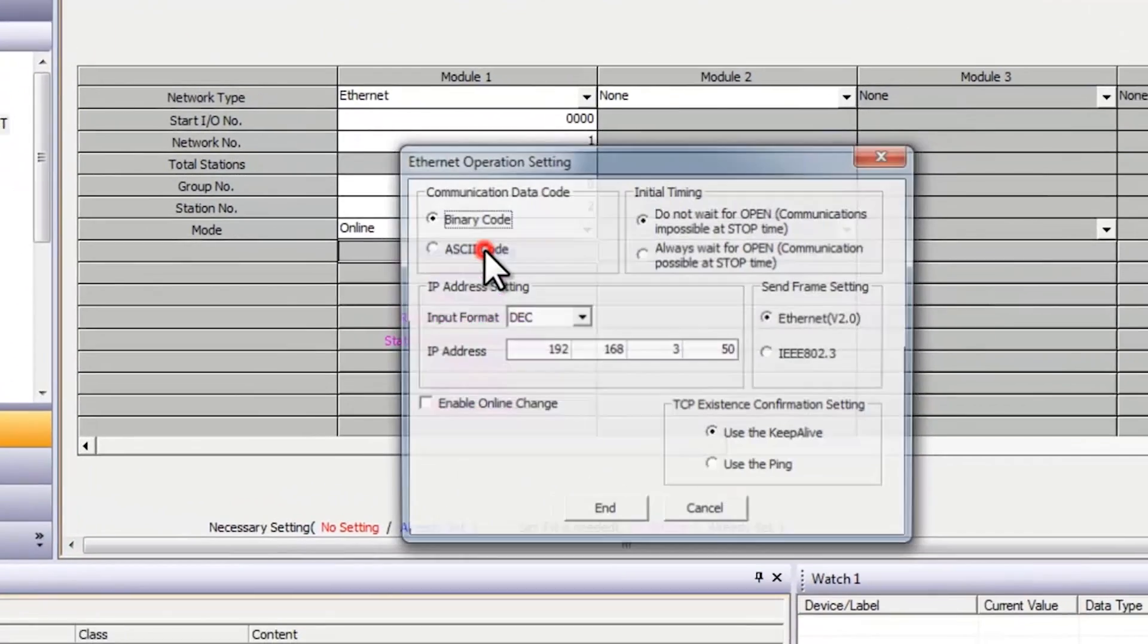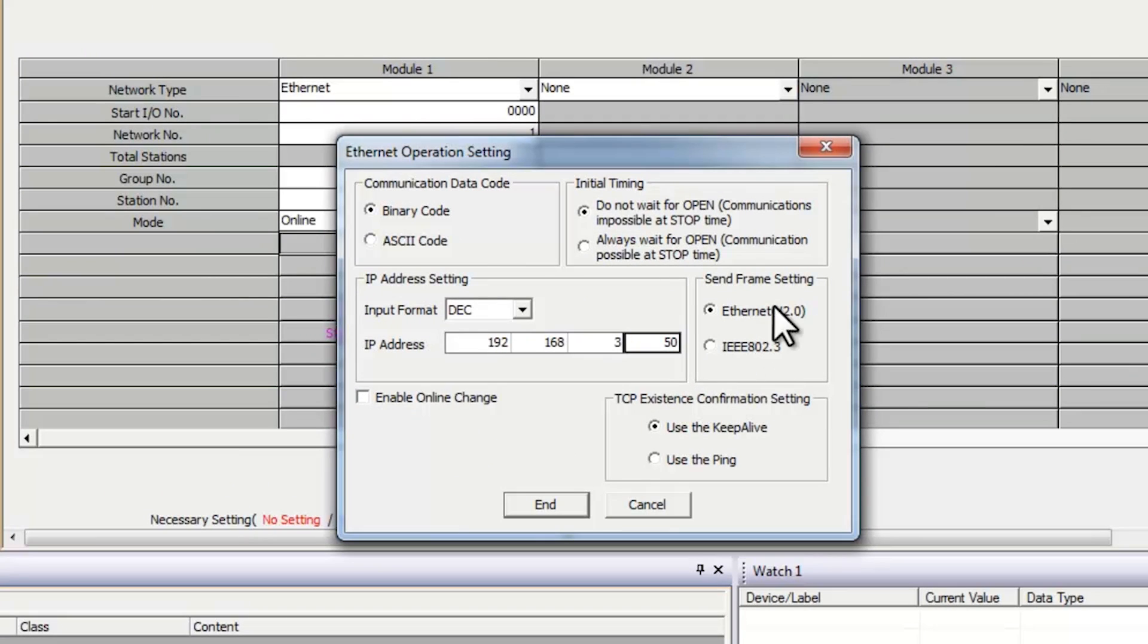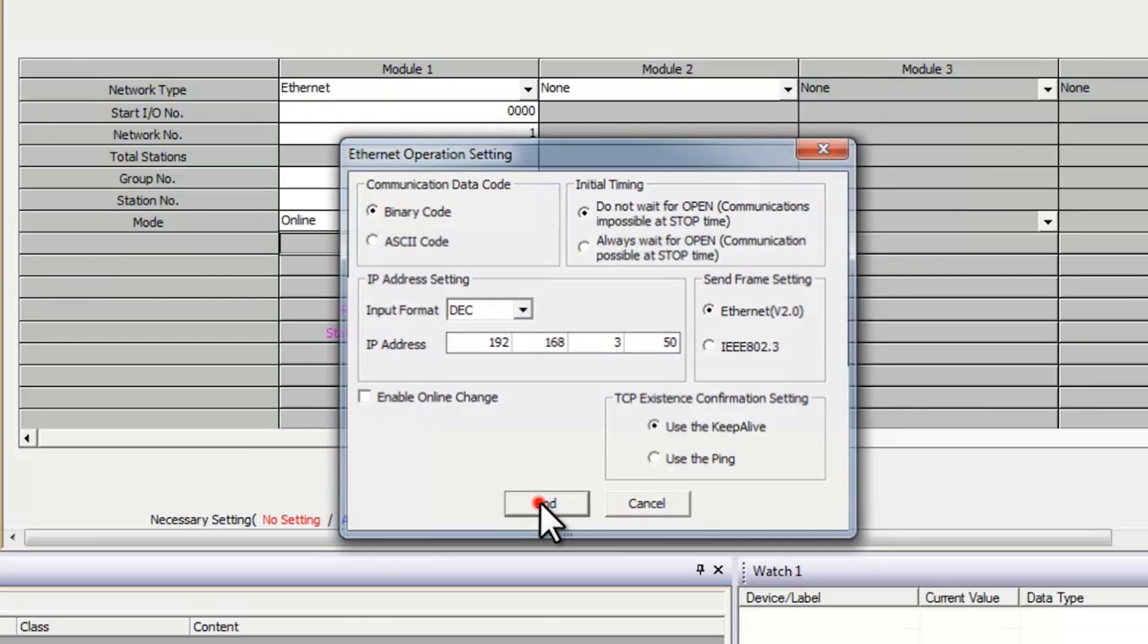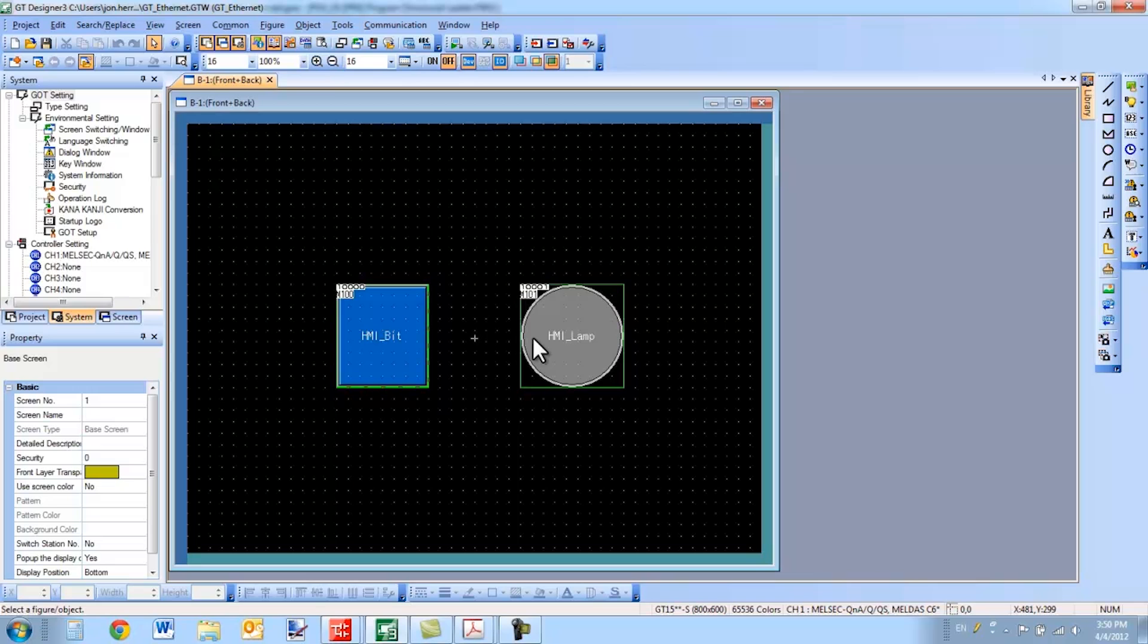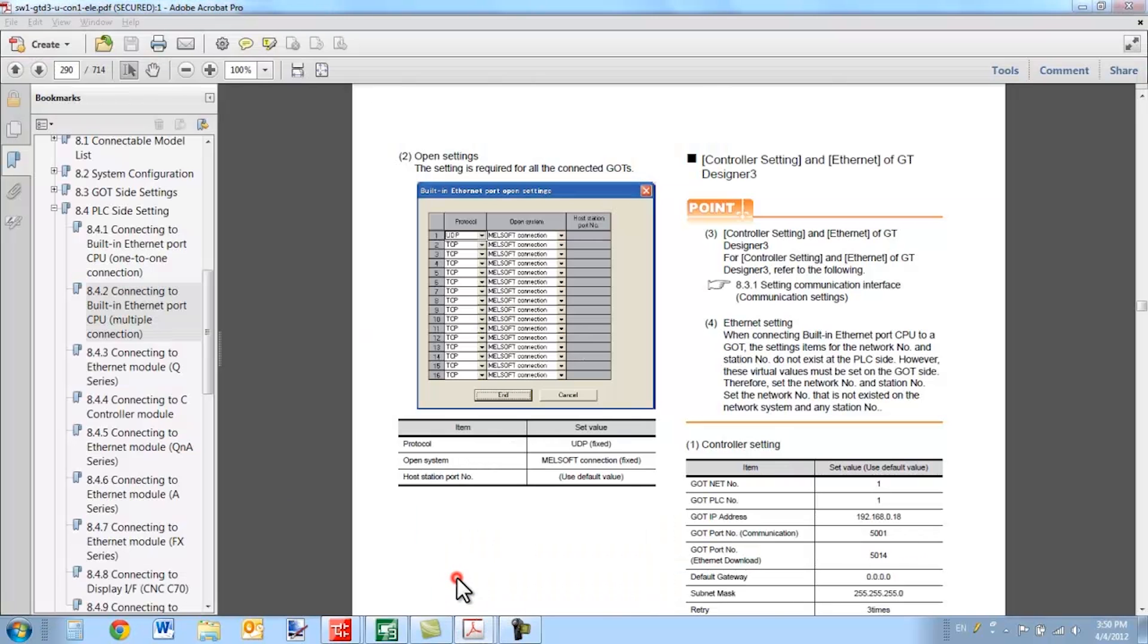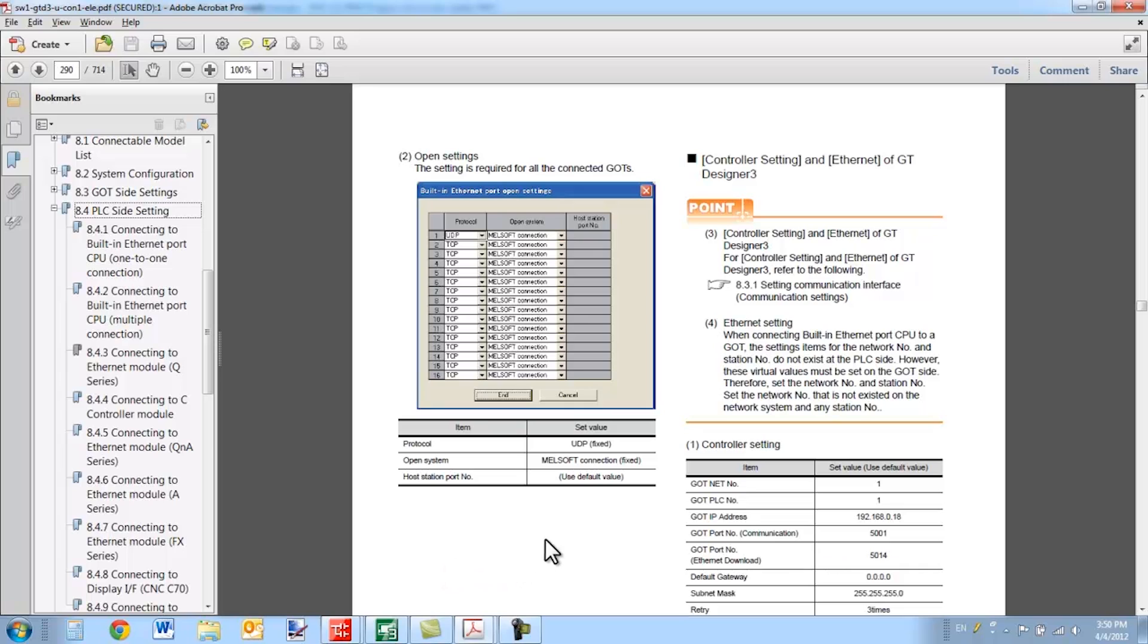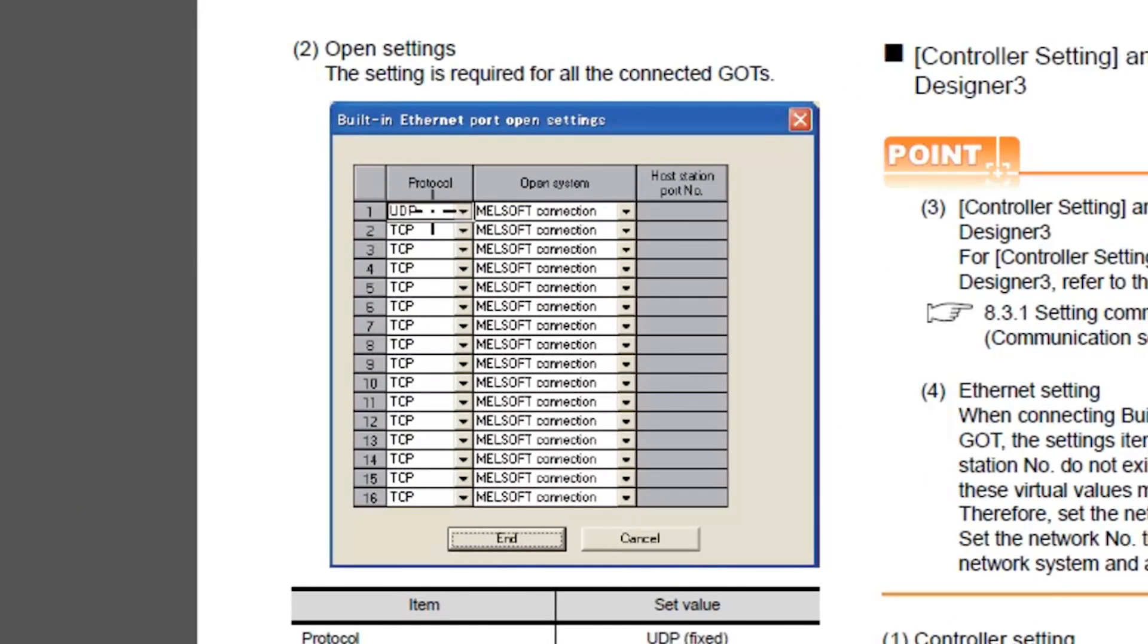And lastly, for the operation settings, configure your IP address. Everything else can remain the same. Other than that, everything should be straightforward. Make sure you refer to that manual for further information specifically related to an FX connection. If you're using a built-in Ethernet port on a Mitsubishi PLC, you need to have a UDP MELSOFT connection open for every GOT you have connected. It's recommended not to overload the built-in Ethernet port on the PLC.